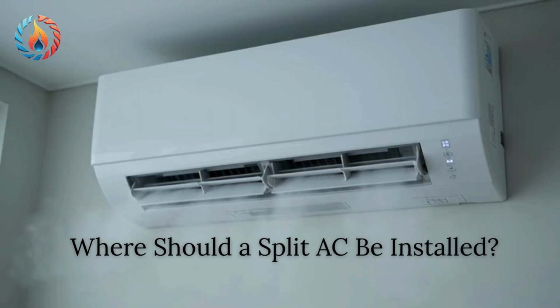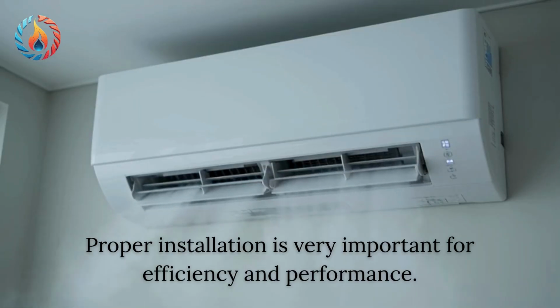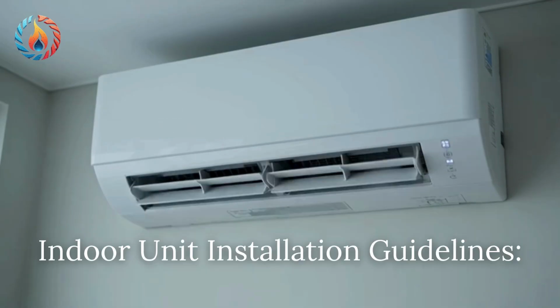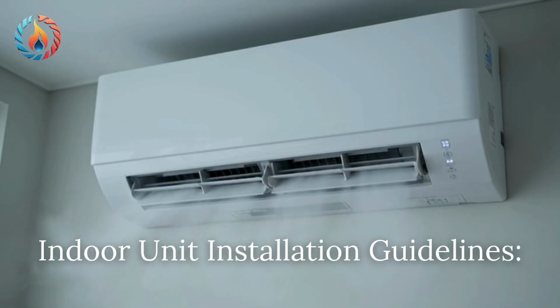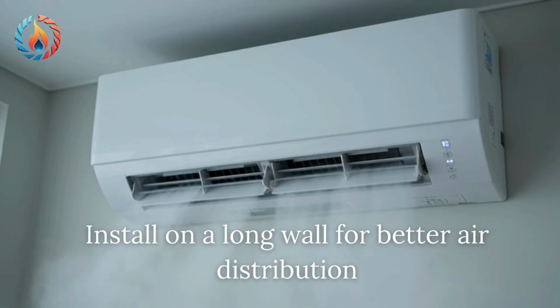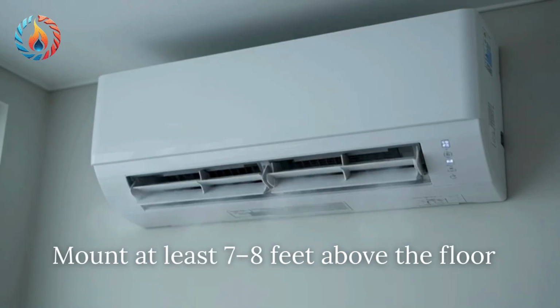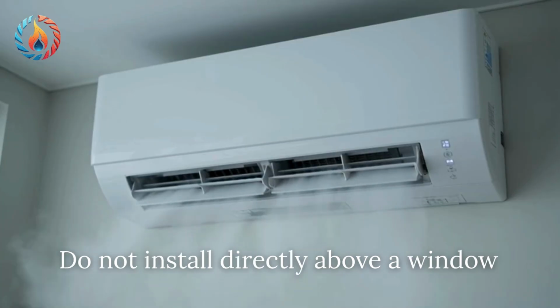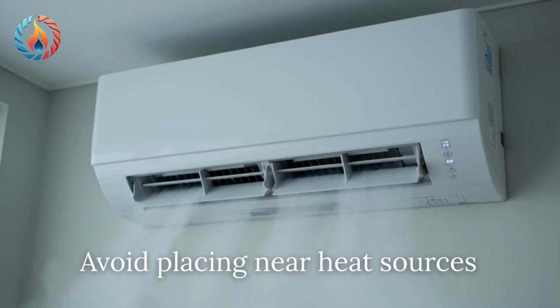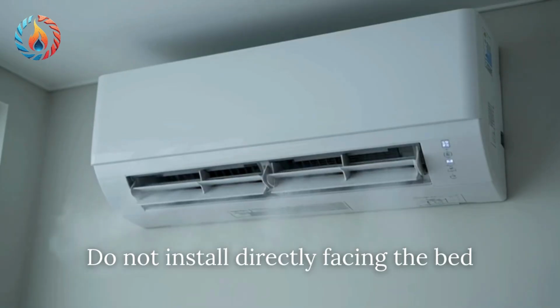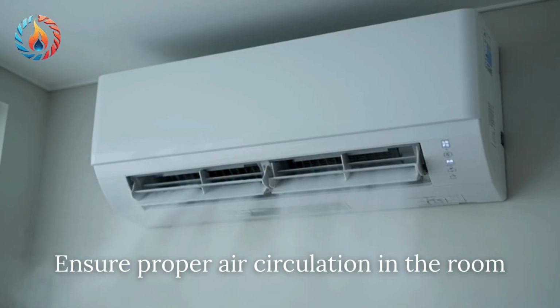Where should a split AC be installed? Proper installation is very important for efficiency and performance. Indoor unit installation guidelines. Install on a long wall for better air distribution. Mount at least 7 to 8 feet above the floor. Do not install directly above a window. Avoid placing near heat sources. Do not install directly facing the bed. Ensure proper air circulation in the room.